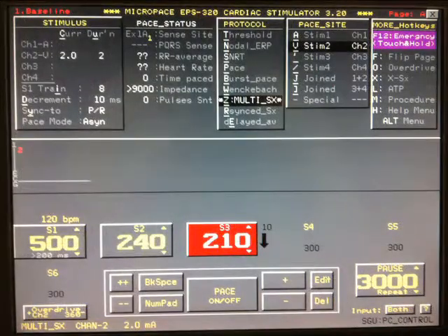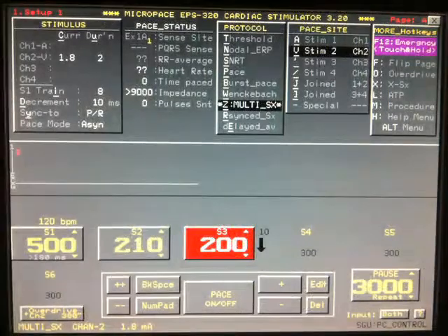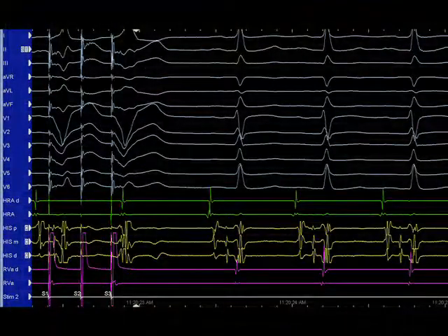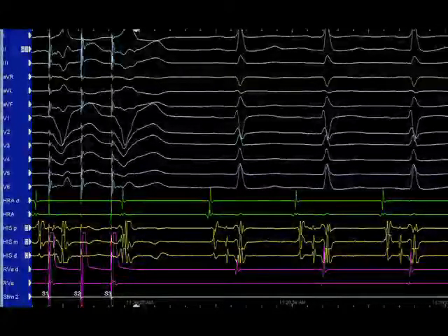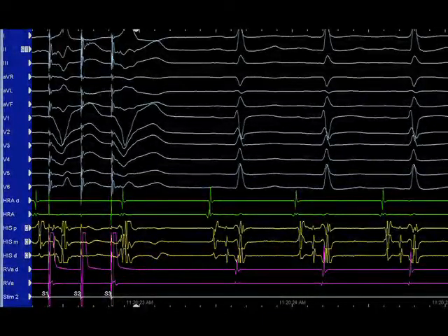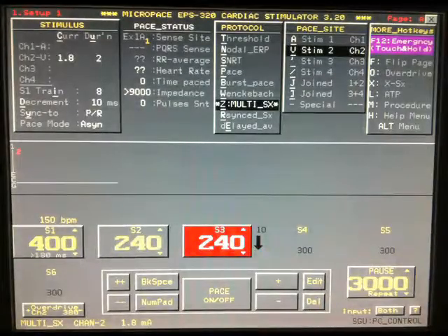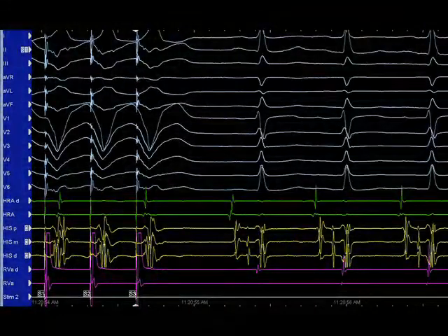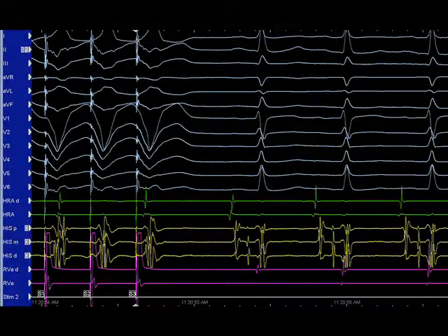If this lower limit is reached or capture is lost, the S2 is then decreased by 10 milliseconds and S3 increased by 10 milliseconds. S3 is decreased again until capture is lost or the lower limit is reached, and then the S2 is decreased again until capture is lost or the lower limit is reached. Here, at a drive of 500 milliseconds, S2 of 210 and S3 of 200, there is loss of capture of S2. This process is then repeated at the pacing drivetrain of 400 milliseconds, with the S2 and S3 30 milliseconds above ERP, or 240 milliseconds in this case.